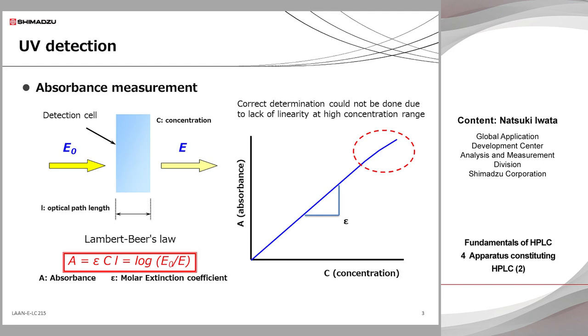The linear relationship between the absorbance and the concentration of the sample compounds is guaranteed up to a certain concentration, so it is important to determine the concentration within this linear relationship range, called dynamic range. If the concentration is too high, the increase in absorbance is saturated, as shown in the graph on the right side. This phenomenon can be understood as a state in which the absorption of light is suppressed, because the sample compounds overlap each other in a cell at a high concentration and the shadow of the preceding molecule interferes with the full excitation of the following molecule.